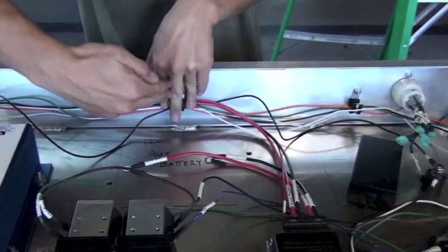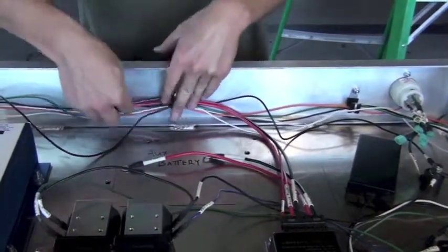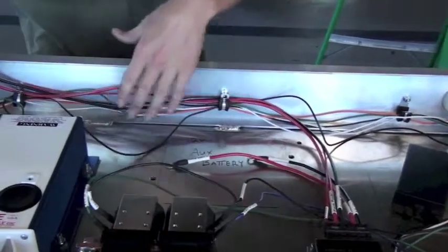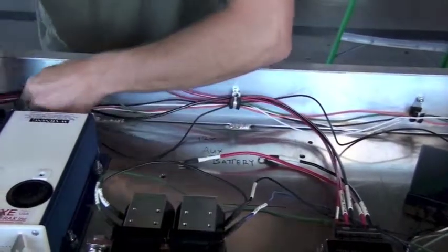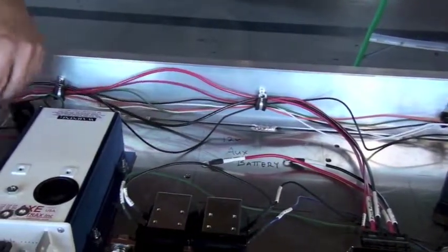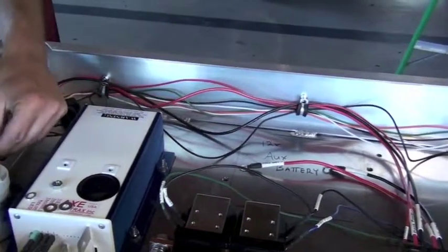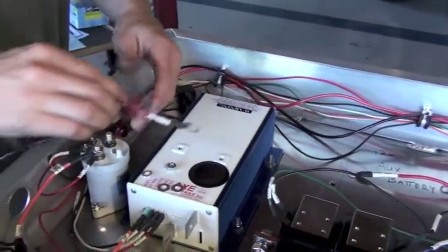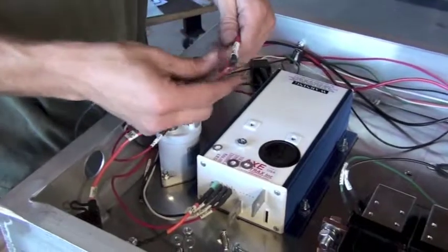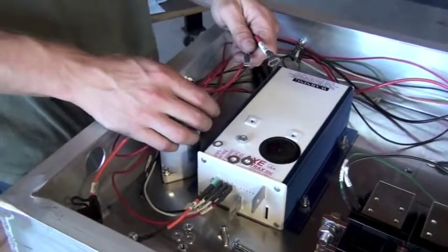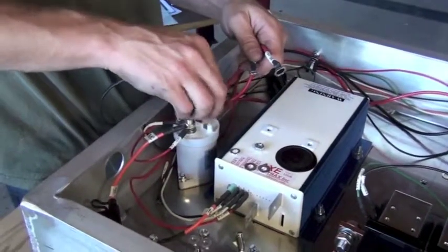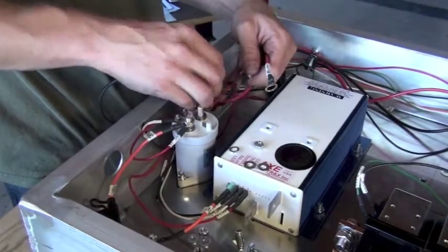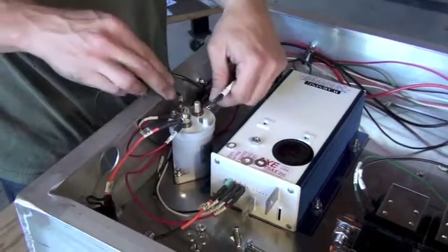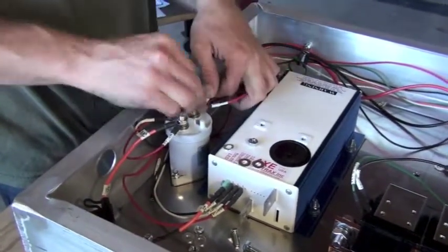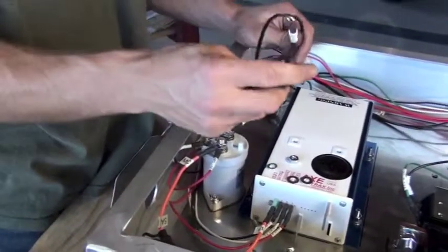Remember that the battery is going to go into position, so we need to route the cable around it through the cable runs and over to the contactor. So just fit every cable in nice and neat, go back around to the contactor, and then we'll put the two connections onto the positive side of the main contactor. So we'll put these two red wires onto the plus A1 terminal on the main contactor. And the black cable goes to controller B minus.